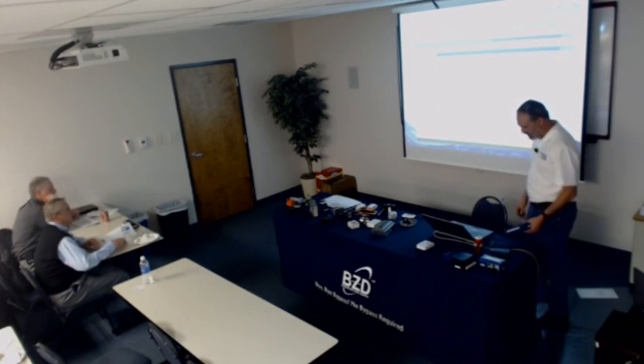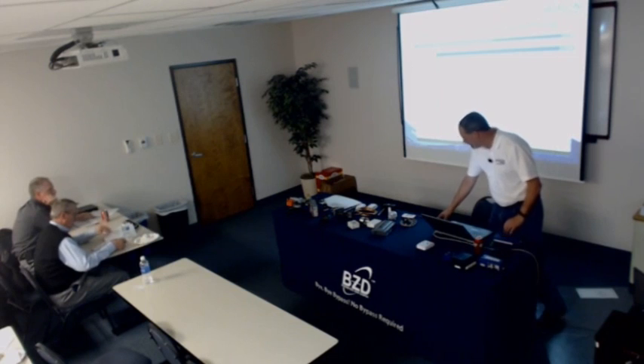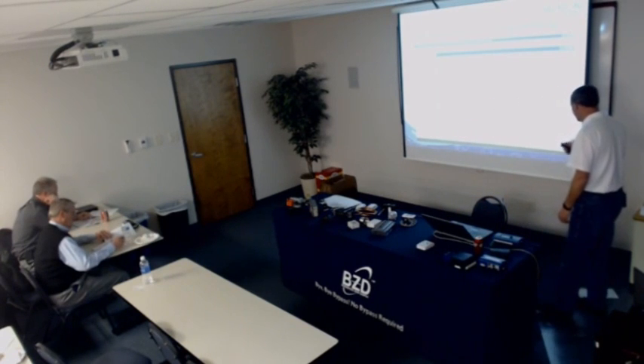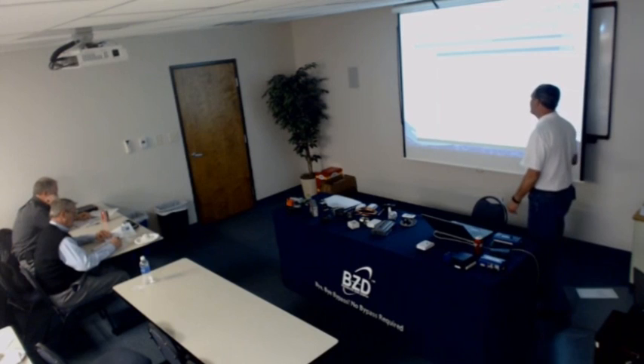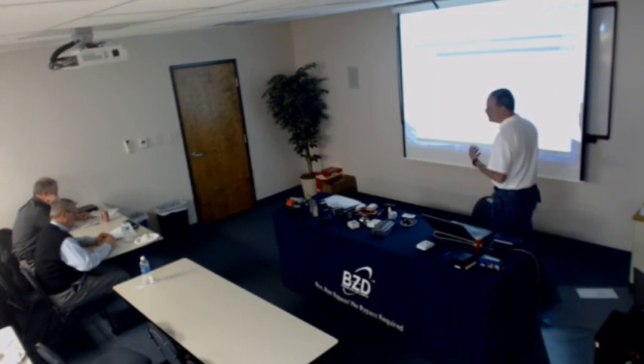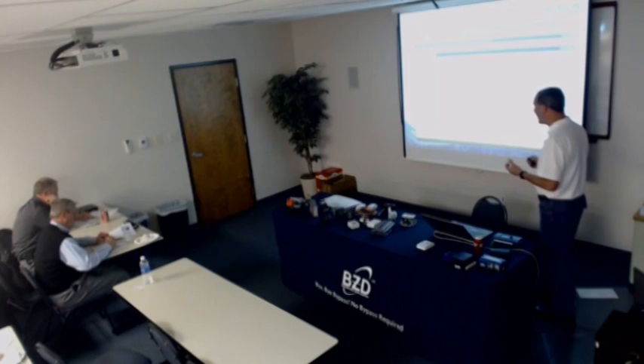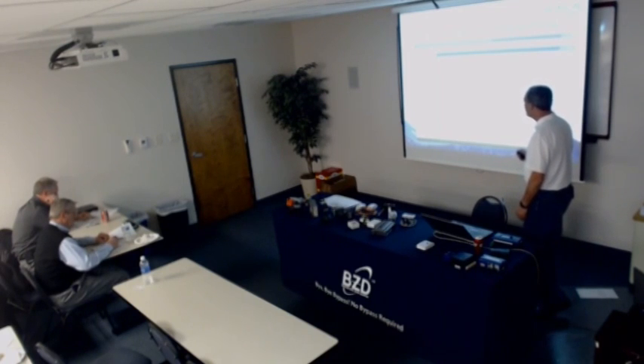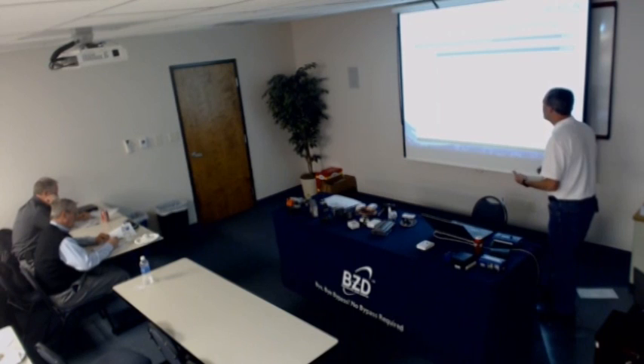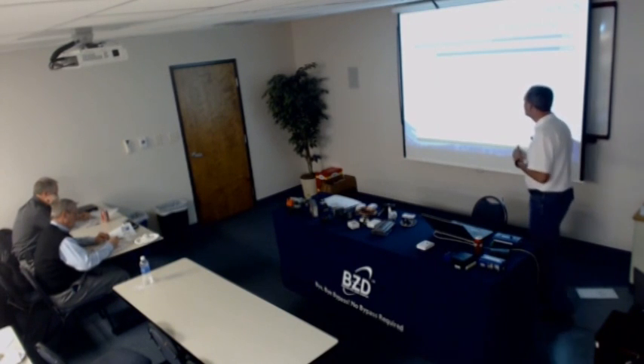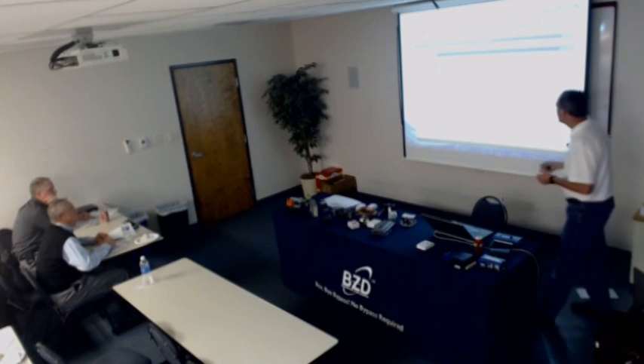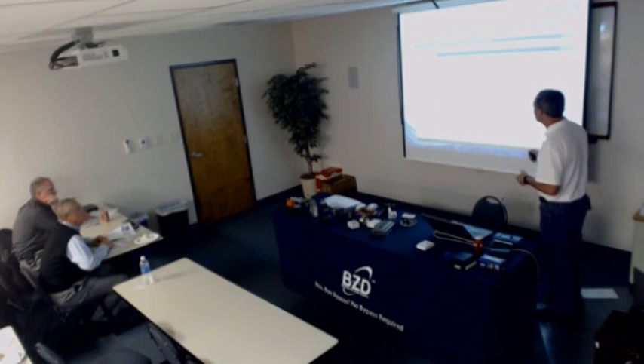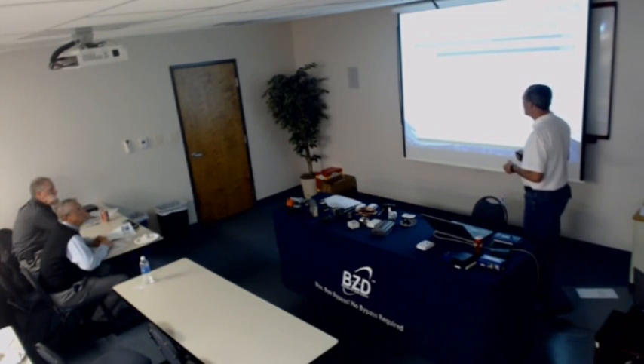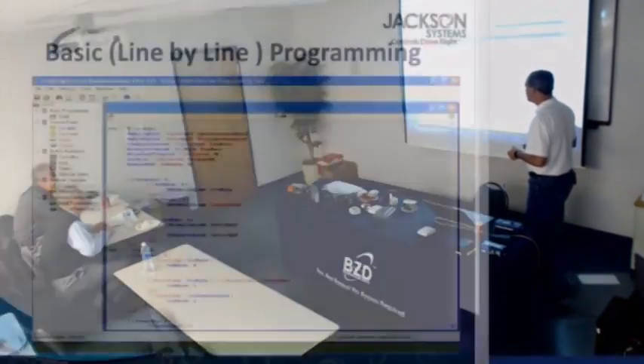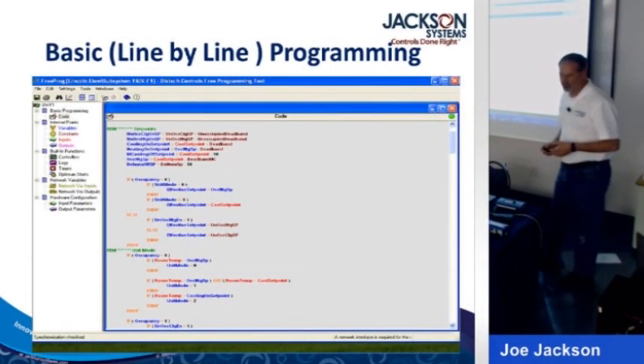So this would be line by line or BASIC programming. You know, it's got a lot of ifs, elses. You define terms. It says if the occupancy equals 0, which happens to be occupied, then the unit mode equals 0. Then you can just see that just even reading that can be tough. It's tough for me to read it, and I wrote it. We haven't used this kind of programming in almost 5 years. But this is just a little bit of programming to check to see if the unit's occupied and to see which set of set points we're going to use, whether we're going to use a heating set point or cooling set point.